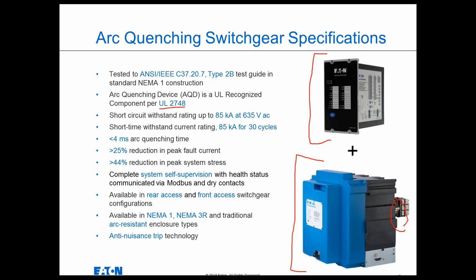The switchgear itself has a short circuit withstand rating of 85 kA at 635 volts and a short time withstand current rating of 30 cycles. And the entire system can operate and quench an arcing fault in less than 4 milliseconds. I'll go into a little bit more detail on how it does that in a couple slides. But that's what drives the incident energy down to extremely low levels, because 4 milliseconds is about a quarter of a cycle. So typically, with other incident energy reducing methods, we're talking a matter of cycles to actually clear a fault, not less than a cycle.